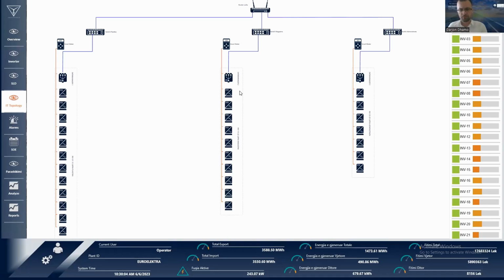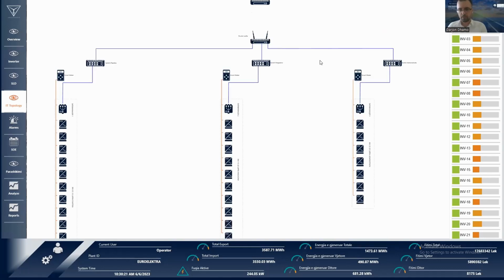Also, in the warehouse, we have 10 inverters. They are communicating with a data manager, and also there is a smart meter, which is communicating again with Modbus RTU with the data manager. And the third is the administration place, where we see 7 inverters communicating with the data manager through the same protocol, SolarNet, and the smart meter communicates with this data manager through Modbus RTU.